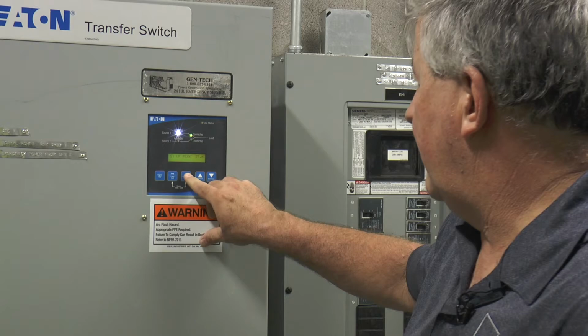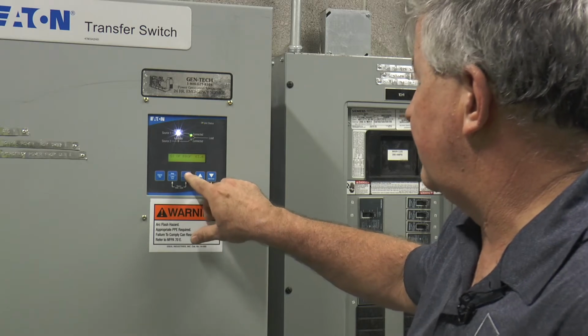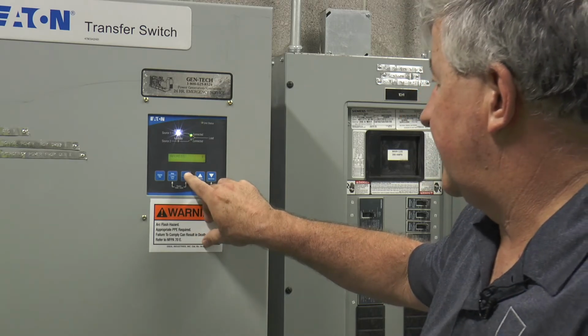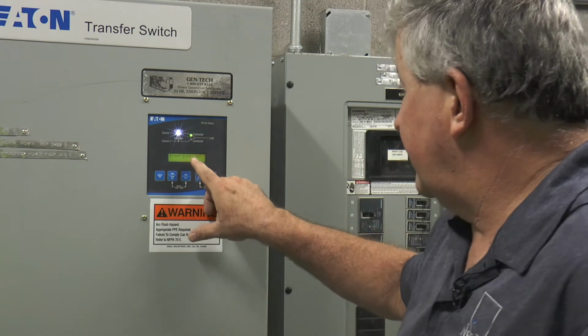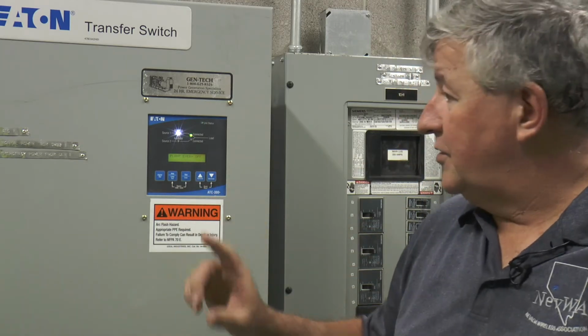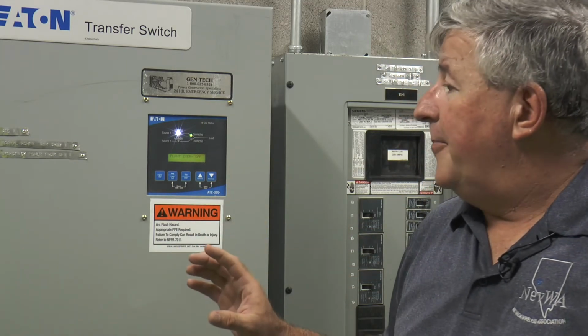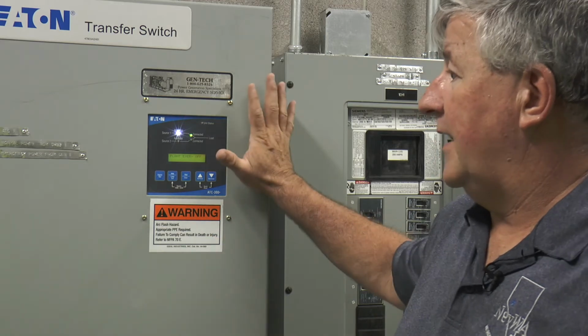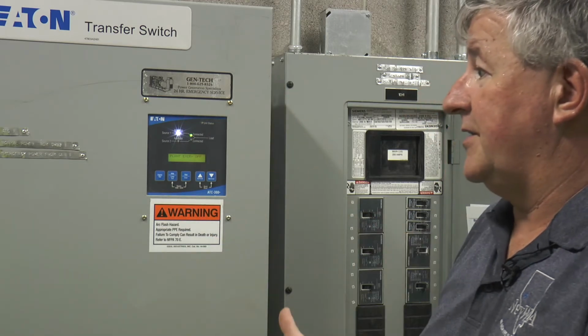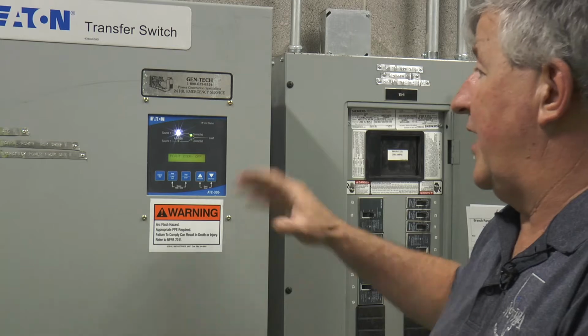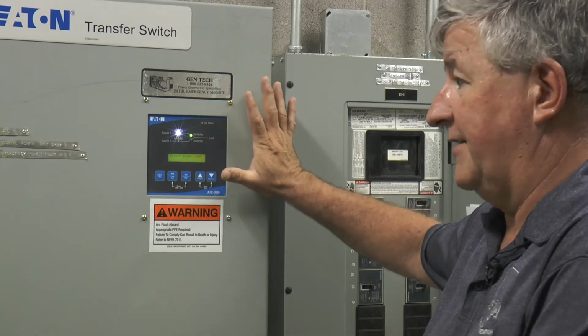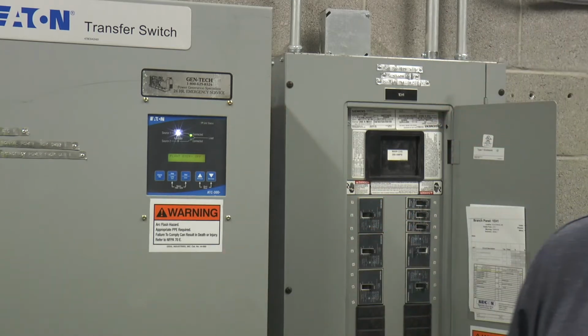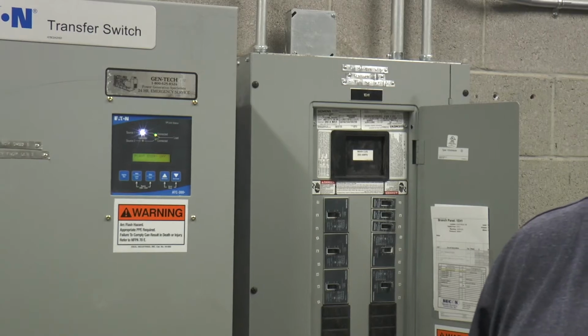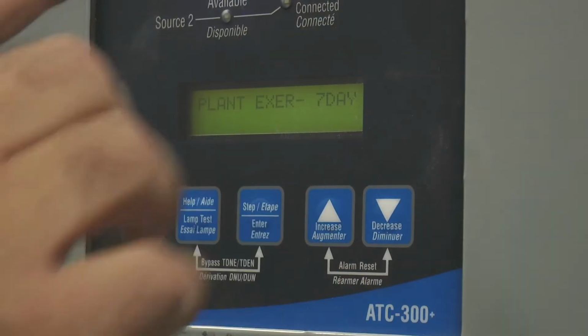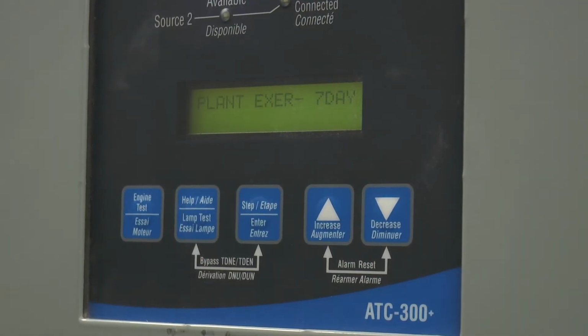The one I wanted to check, it should be set up on this one typically, is your plant exerciser. Plant exerciser is off on this one. We'll check it on this one. Typically we do it on the life safety switch because it's the one that's always on, and if you had to do a transfer test, you always know it's the life safety switch. Yes, they set the exerciser up on this switch. We can leave it there or we can transfer it to here.